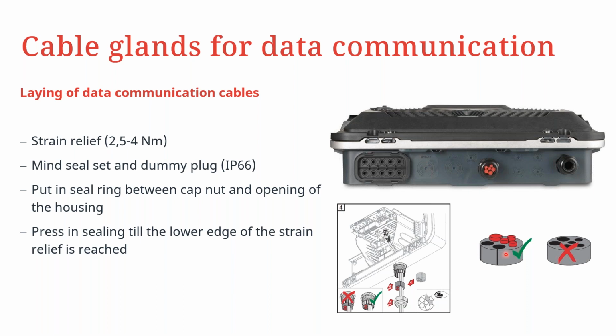Therefore, take out only the knockouts that are required for the number of cables to be used. Once you do that, the seal ring, which is this particular part, is put in the opening between the cap and the opening of the housing, and then you press it in until the lower edge of the strain relief is reached. The tightening torque for this cable gland is from 2.5 to 4 Newton meters.